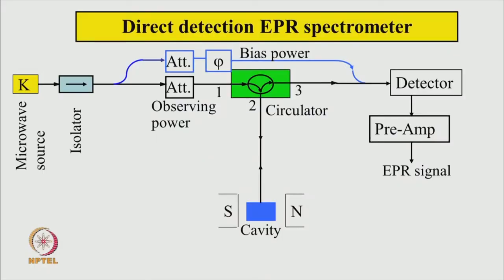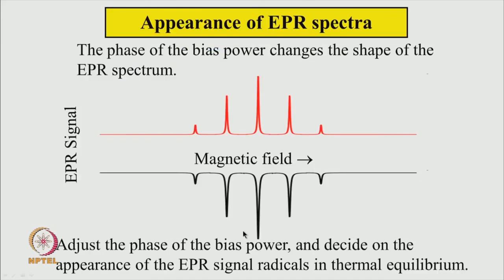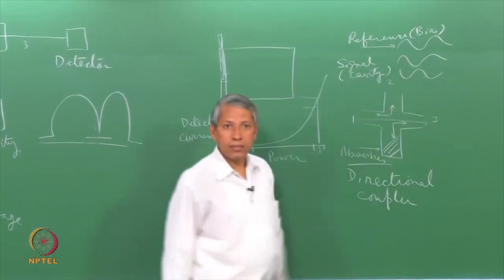What we have so far is called the direct detection EPR spectrometer. The detector signal generated is passed through a broadband preamplifier and we can get the EPR signal. To get the signal, I scan the magnetic field and record the output as a function of the magnetic field. The spectra will look like this - say, some hypothetical radical gives 5 lines. If you change the phase of the bias reference power by 180 degrees, the detector signal changes sign, so the spectrum can flip.